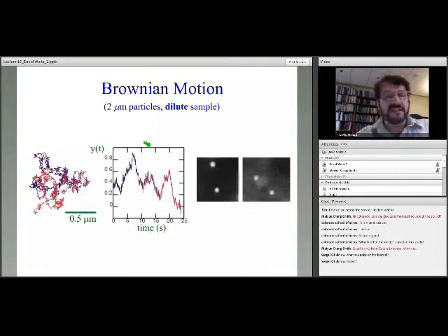And since it's a sphere, you know what its diffraction pattern is. And to identify the location of that can be done much, much more precisely than the Rayleigh criterion, lambda over 2, would suggest. You can actually identify the location of a particle using a confocal microscope easily to, say, 20 nanometers. It's limited only by the signal to noise. In fact, if you have a better signal, you can find it even more precisely.